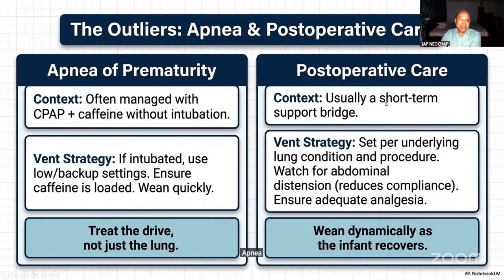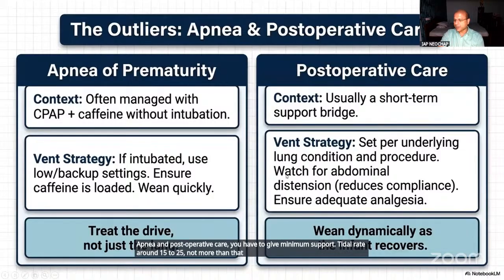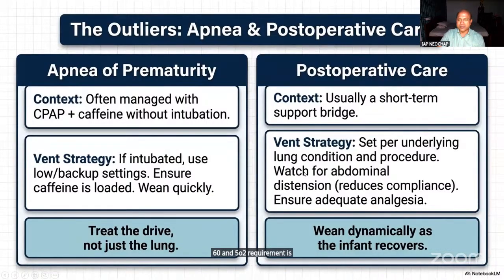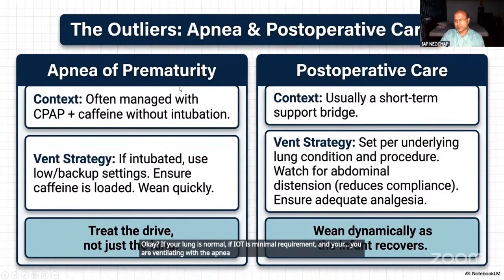For apnea and post-operative care, you have to give minimum support. The rate should be around 15 to 25, not more than that. This is a common mistake. Babies with HIE are ventilated with the rate set at 60, FiO2 requirement 21, and pressure just 14/5. That should not be there. If your lung is normal and FiO2 requirement is minimal, and you are ventilating for apnea, like apnea of prematurity or maybe HIE, your ventilator rate should be 15 to 25, not more than 25.